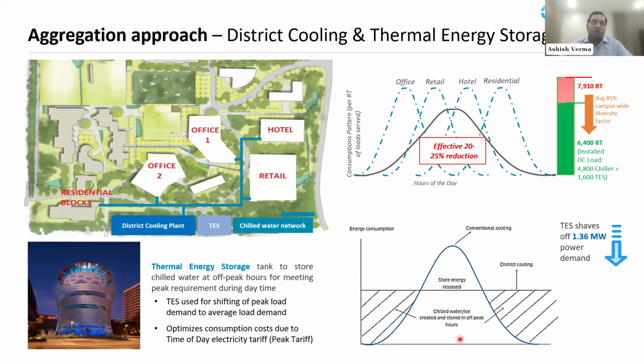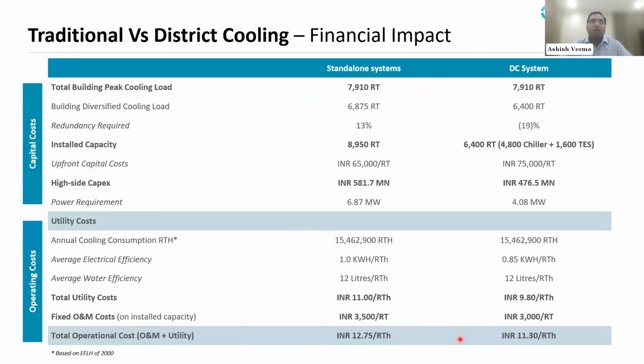One more thing worth noting here is that for residential blocks, like Dr. Garg gave an example where the residential peak was 4,000 and installed capacity was somewhere around 340. Here, if we have a mixed use development, probably we need not install even 340, because residential buildings could be catered through the equipment which is supplying in the daytime for the office and other areas. So this is one of the advantages when we have a mixed use kind of development.